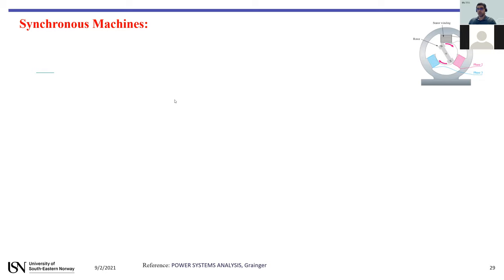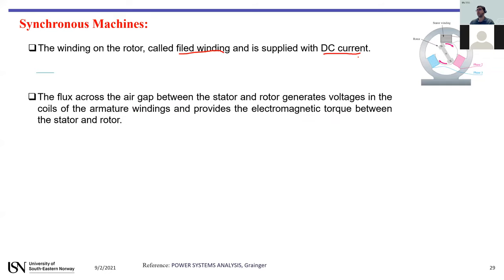In a synchronous machine, the winding on the rotor is called field winding, and it's supplied by a DC voltage and DC current source. The flux that crosses the air gap — the air gap being the space between the stator and the rotor — generates an induced voltage in the armature coil.